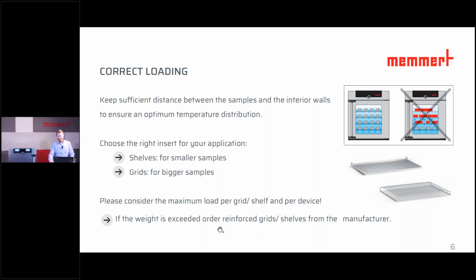This is actually around 20 to 30 kg per shelf or grid in standard. Many manufacturers also offer reinforced versions, which then have a load capacity of up to 60 kg. The use of these reinforced inserts often requires a special interior design, which cannot be retrofitted later. So the maximum load should ideally be known when purchasing the device already.